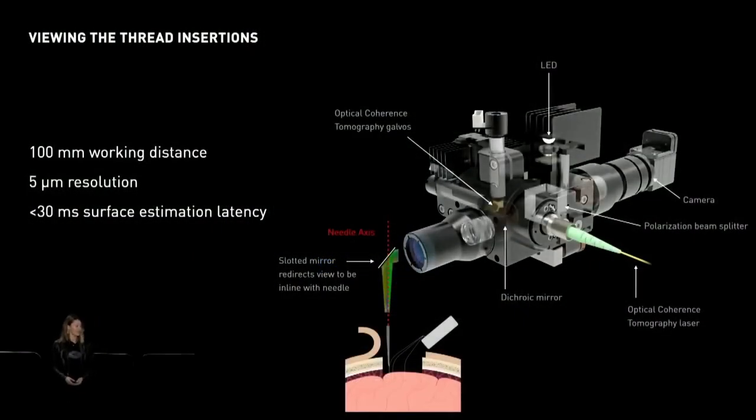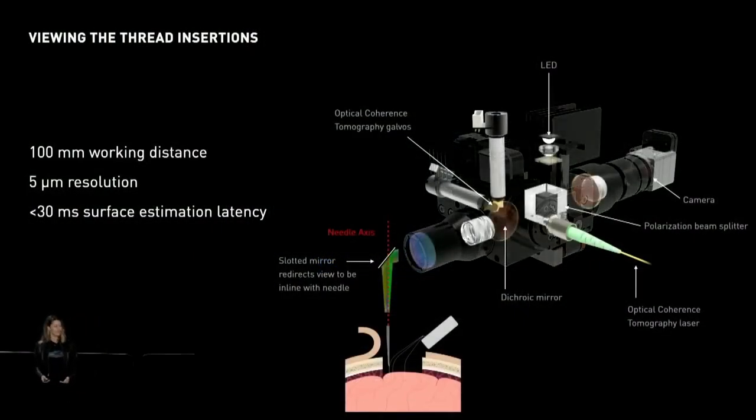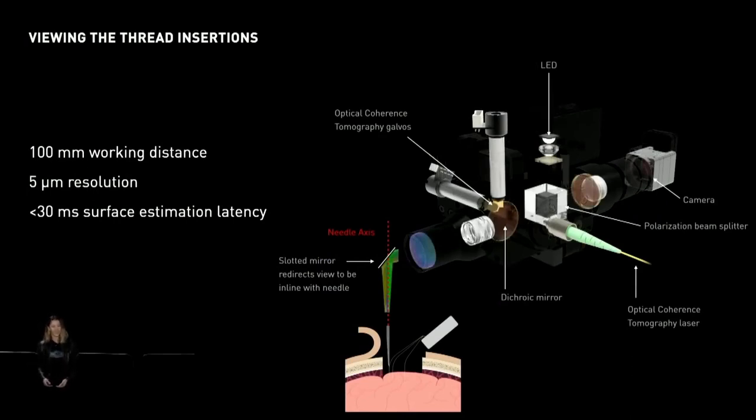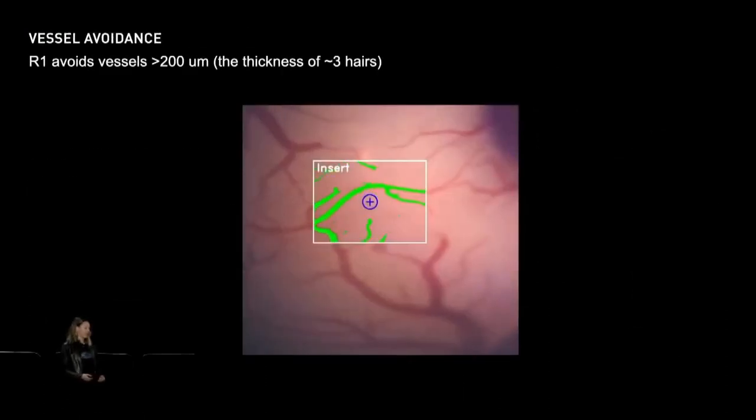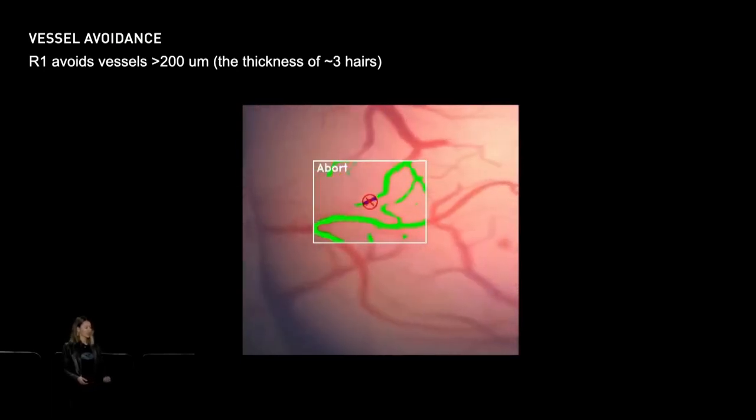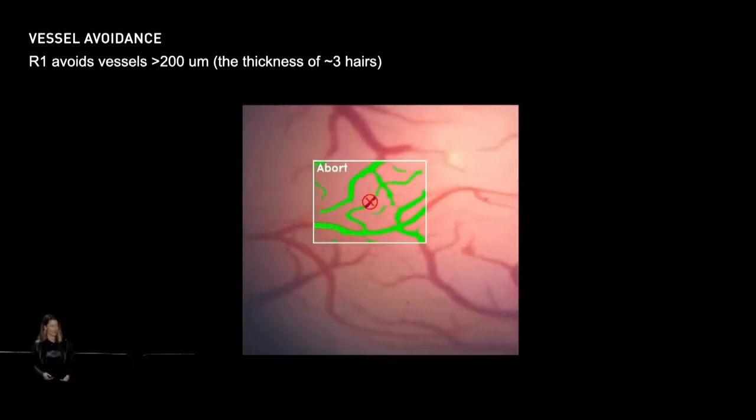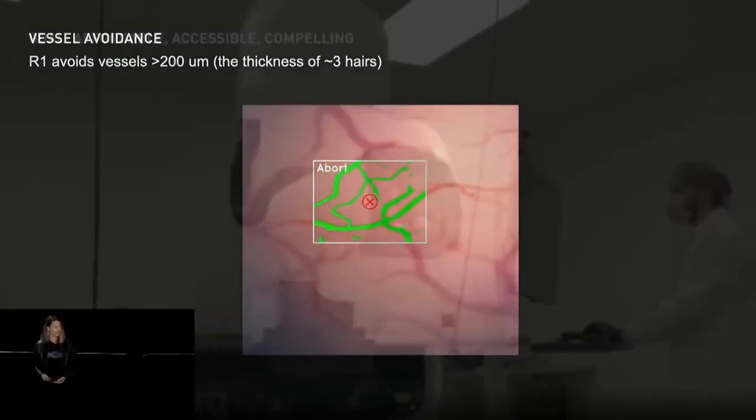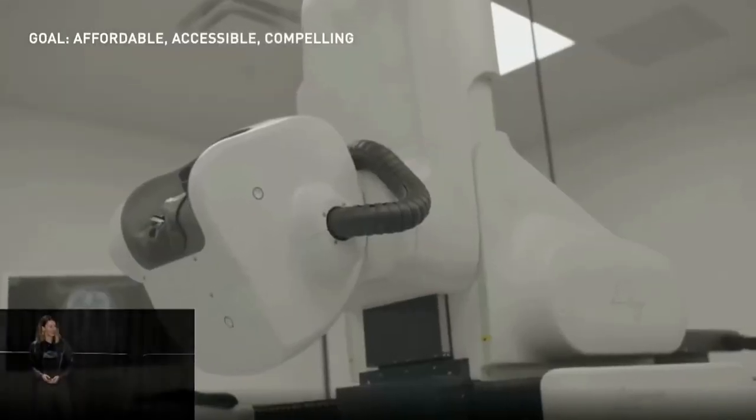The way that the team solved this is by putting all three of these optical paths into one optical stack using photon magic or polarization, whatever you want to call it. And that enables us to do vessel avoidance in real time. As I mentioned, the brain is moving, and where we place targets in the beginning may not be where you want to insert at the moment the needle's going down there. So the robot can actually detect the vessels and then determine if we're going to insert onto a vessel or not, if it's safe to insert, and then that way we can avoid inserting onto major vessels. And that brings us to the robot that we have here today.